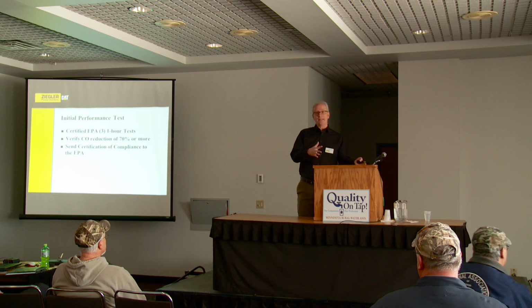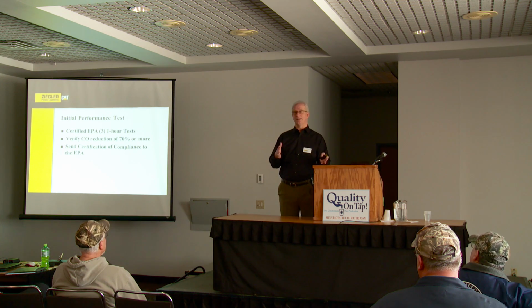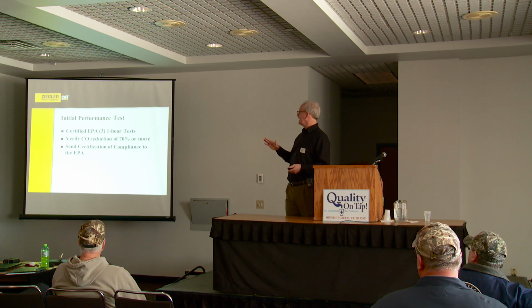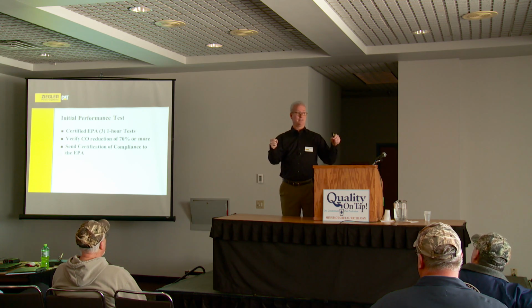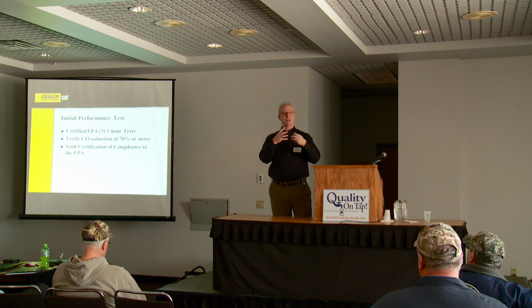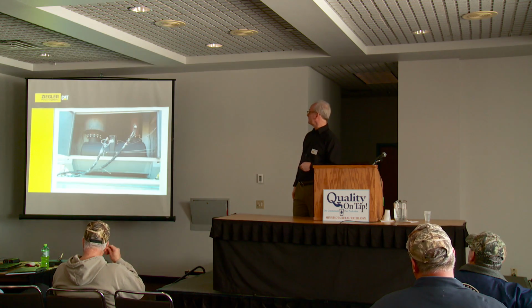So after you've installed the catalyst, what you need to do is have it certified, and there are companies out there that do it. The EPA has specific rules on how you do that. 3 one-hour tests. They take all this certified equipment, hook it up, measure the gas before it goes in the catalyst, measure the gases coming out the exhaust stream, and say, yep, it's been reduced by 70%. You gather up all that certified data, and you submit that to the EPA and say, look, it all works.